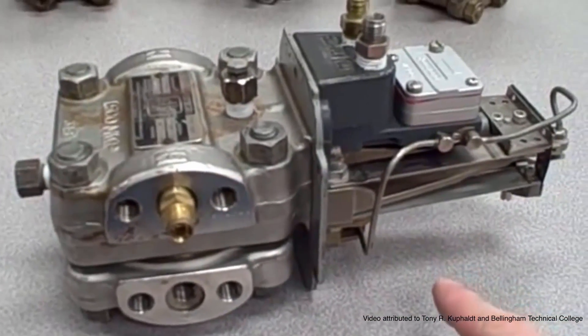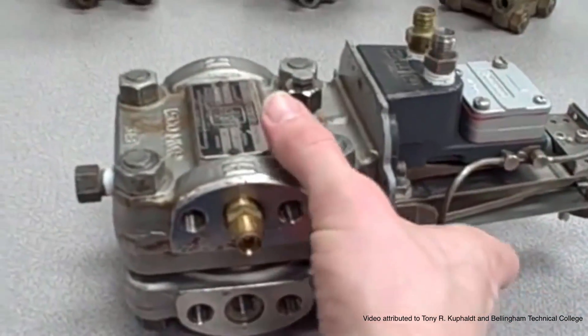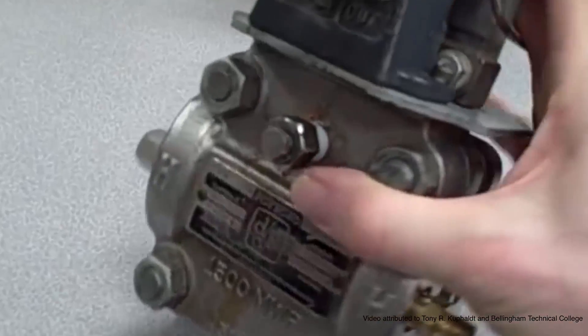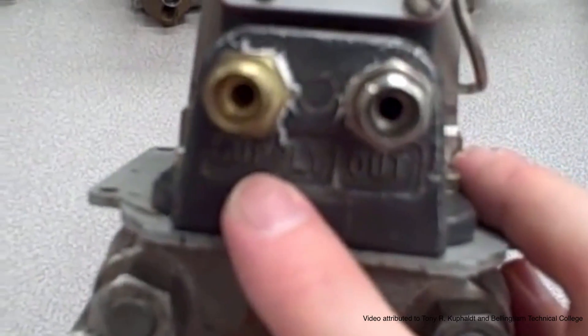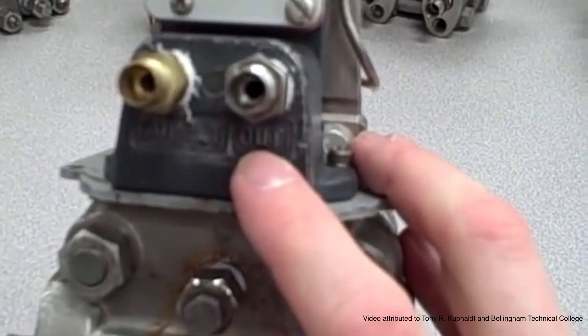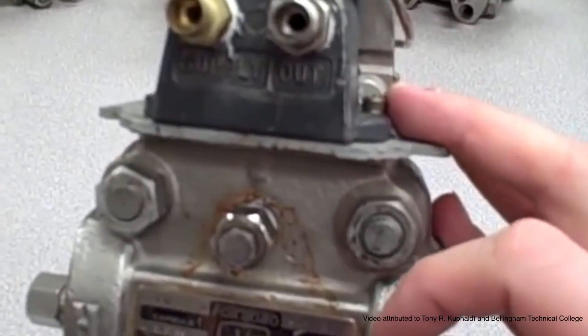Lying down on the table is a Foxboro Model 13A Differential Pressure Transmitter. This particular pressure transmitter is pneumatic — it has no electronic components whatsoever. It receives a supply pressure of approximately 20 psi clean instrument air and provides an output pressure ranging between 3 to 15 psi of clean instrument air, representing the process that it is measuring.